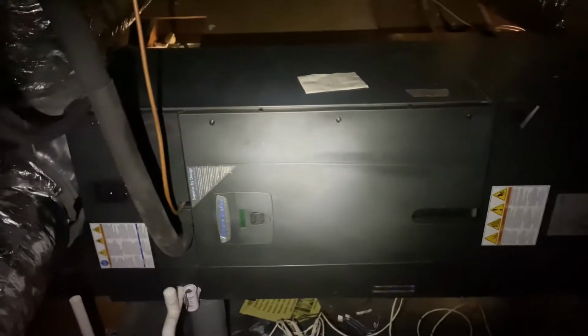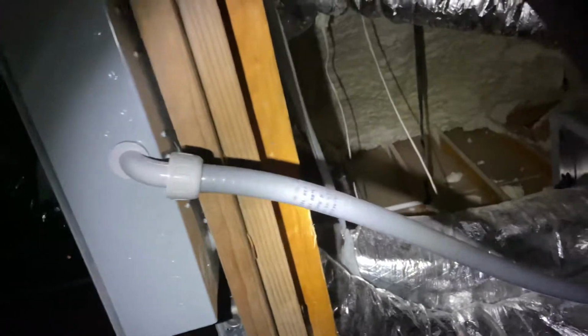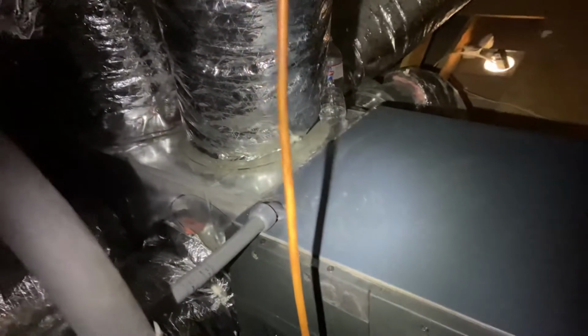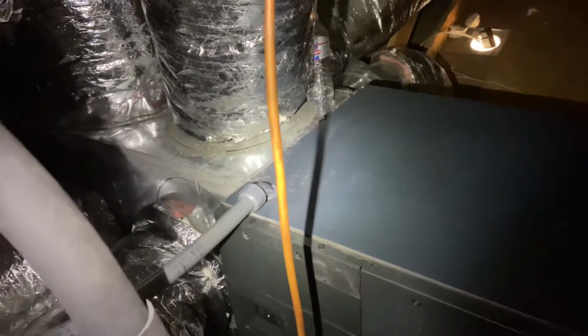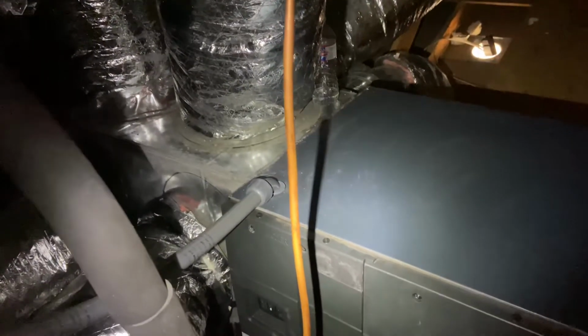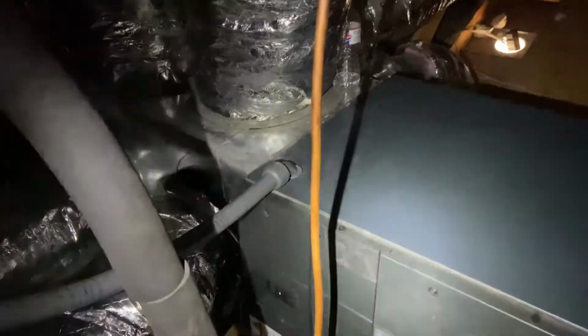So here is the air handler. Now, ideally, this guy would have been mounted vertically, and that's why I'd hoped they would have done, but they didn't. So they had to mount it on its side, which is perfectly fine. And so you can see here is the electrical connection I had to do. So just 3/4 inch conduit running a pair of number 8s, a pair of number 6s, and one 10 gauge ground to power those 2 circuits.